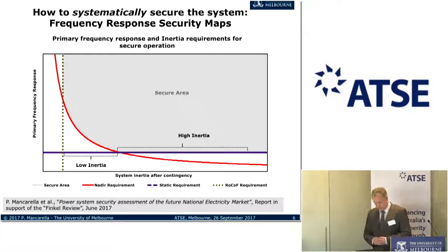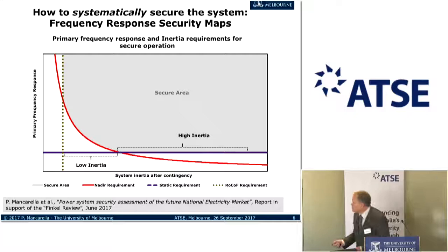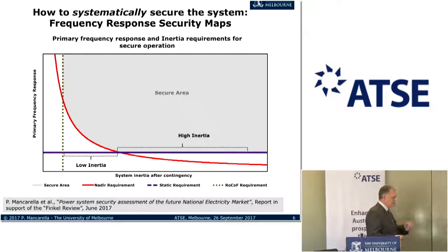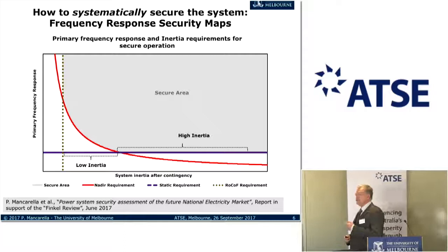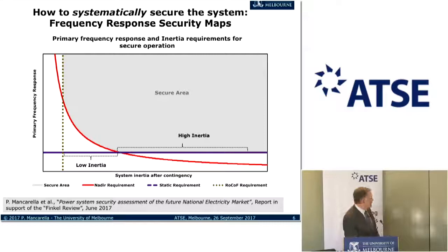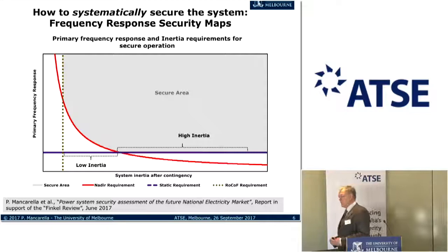The vertical line here at the beginning tells us that we're losing frequency too quickly. It's a rate-of-change-of-frequency requirement—again, not something that comes into play when we have a high inertia system. The red curve has to do with how far we actually drop the frequency. That's the nadir point. We need the nadir point sufficiently high in order to maintain everything.